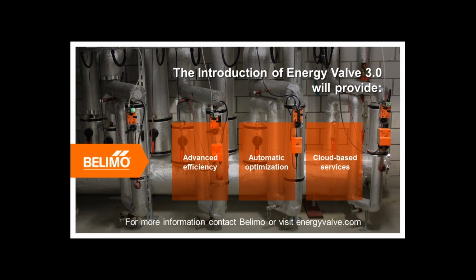Next question. How is the system to be water balanced after the energy saving valves have been installed? Once again, I'm not exactly sure what that question means. Once energy valves are installed, your system is in effect dynamically balanced, working at basically a valve authority of 1. Since the valves are pressure independent, you don't need to use circuit setters or any type of manual balancing valves on the coils. You may have them in the headers to control flow to a floor or something like this, but you wouldn't need to have any type of manual circuit setters.